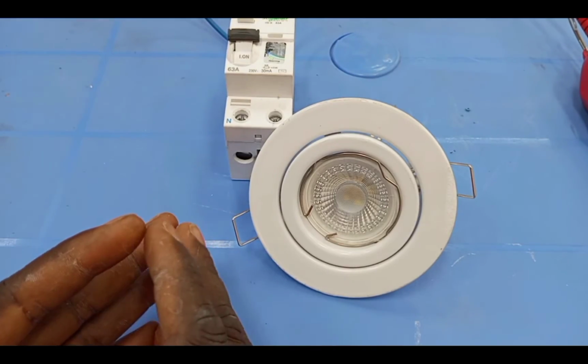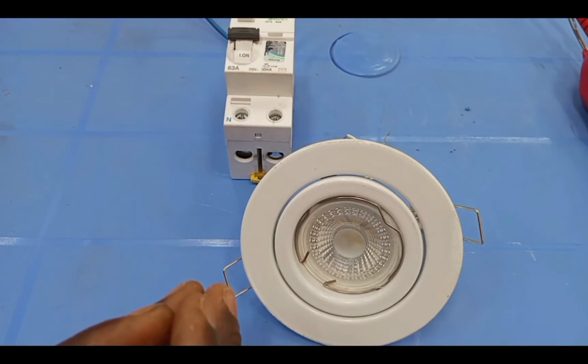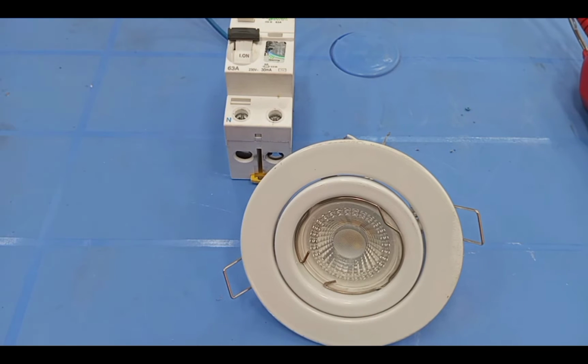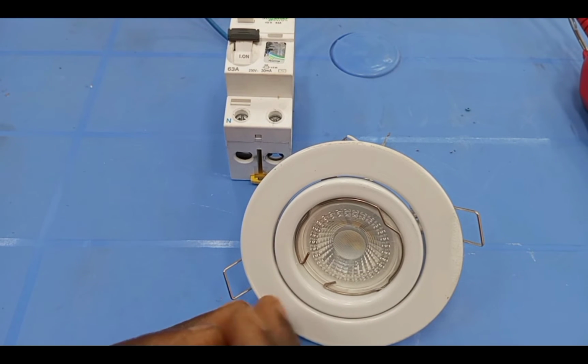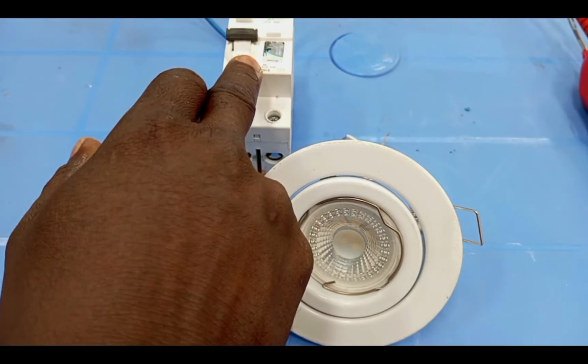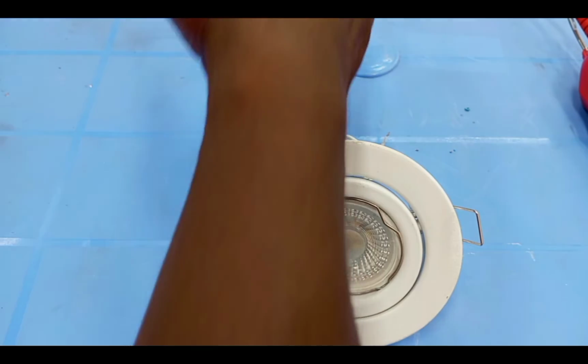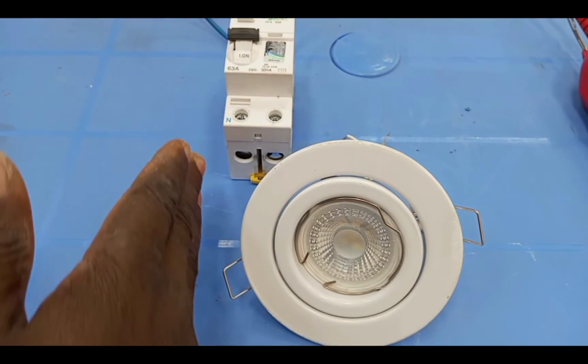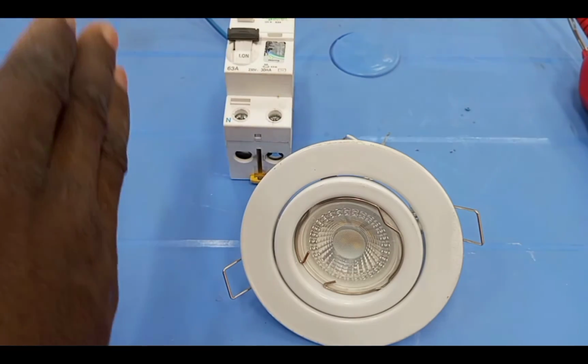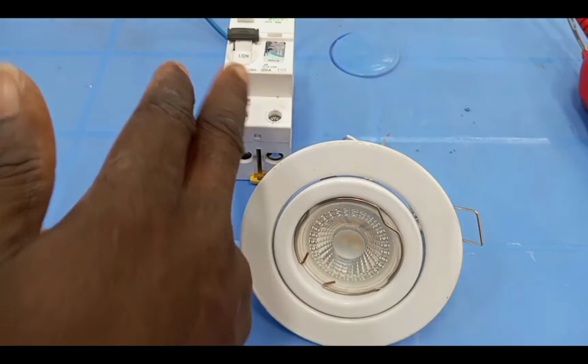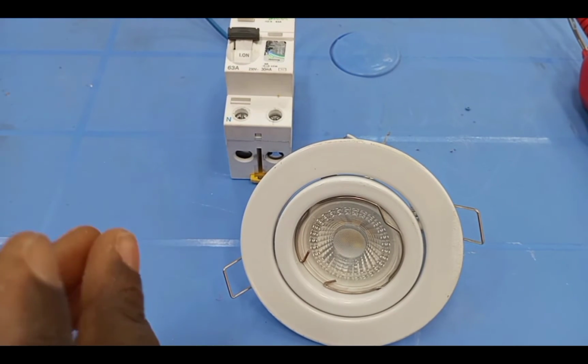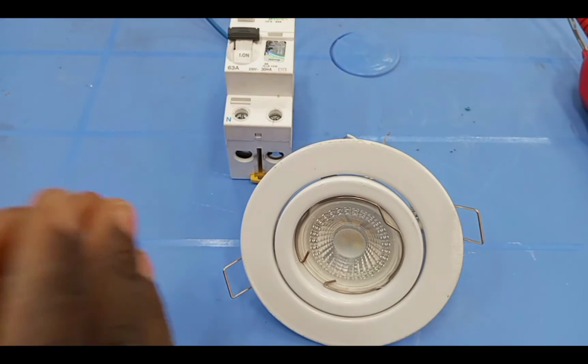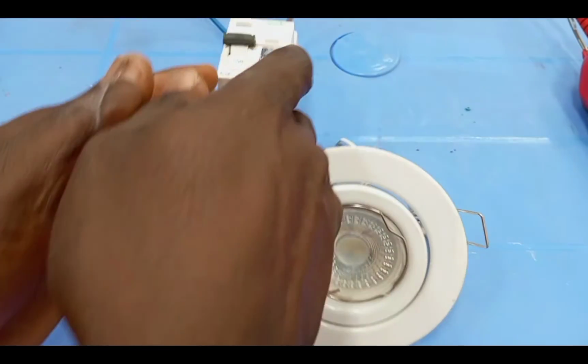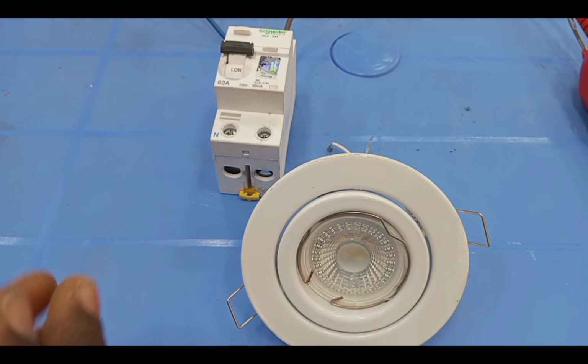Okay, so I'm going to connect this load. When I connect the load, the RCD will monitor the amount of current that this lamp will take. If this lamp is taking 0.02 amps to work, the RCD will make sure that 0.02 amps flows through the live wire, supplies the lamp, and then 0.02 amps flows back through the neutral wire. All right, so in that circuit, the RCD will only permit 0.02 amps through the live and then 0.02 amps through the neutral. And that is what it is going to monitor. That is how it should be continuously.